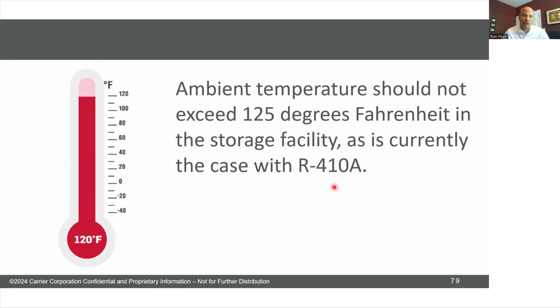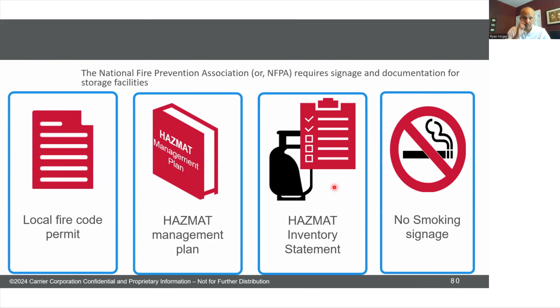I am fully aware that your van at some point in time has probably been 100 above 125 degrees and you did not blow your tanks of refrigerant. There's probably some safety factor in that number. Maybe it really won't blow until you get to 135 or something like that. I don't know. Obviously, commercial kitchen hot water 150 is enough to blow it because everybody gives me that example. But 125 is right there at the border. That's the rule. In either case, it's the same rule as 410A. So whatever you were doing to keep your truck from being too hot before is the same thing you're gonna do to keep it from being too hot now.